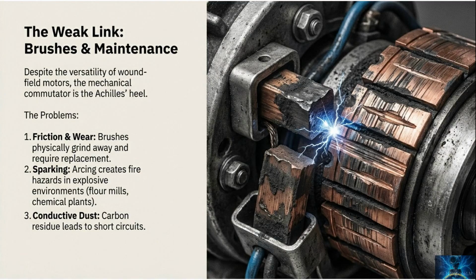This slide is your reality check. Brushed DC motors work, but brushes and commutators are maintenance items. Key issues: friction and wear, requires inspection and replacement. Sparking and arcing can be a hazard in sensitive environments. Carbon dust, conductive contamination that can create shorts and tracking paths. A practical troubleshooting note: brush problems often show up as unstable torque, speed hunting, unusual noise, or visible commutator damage patterns.